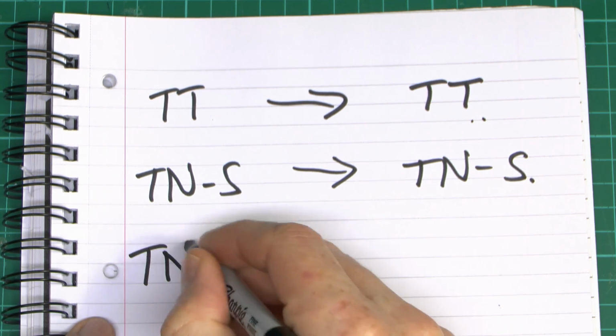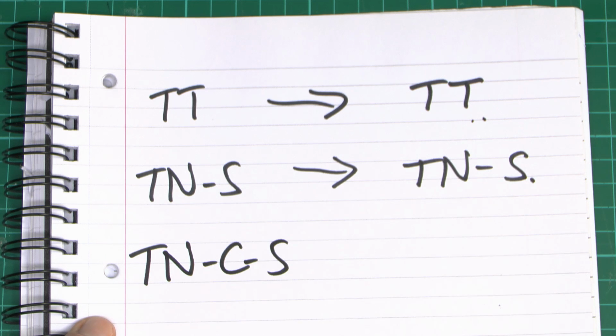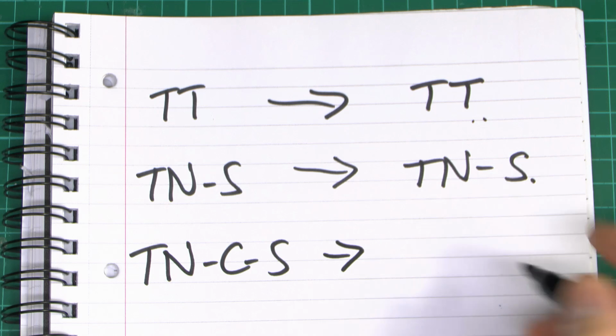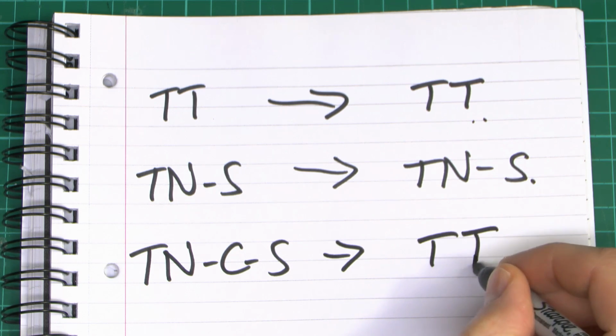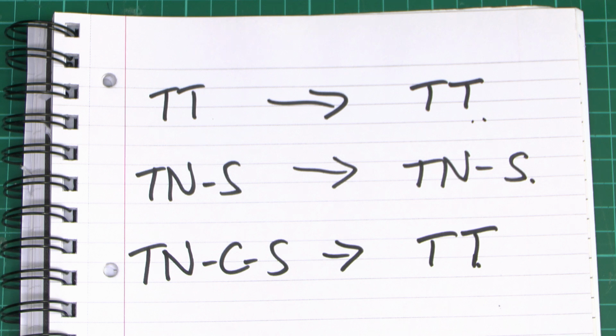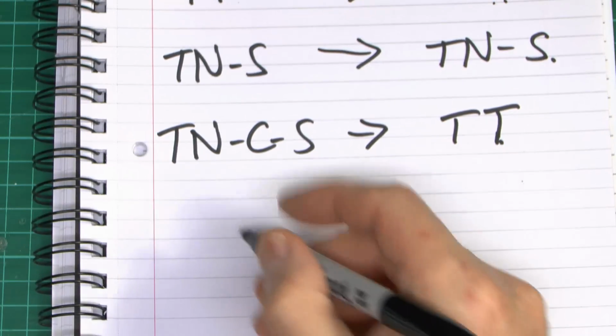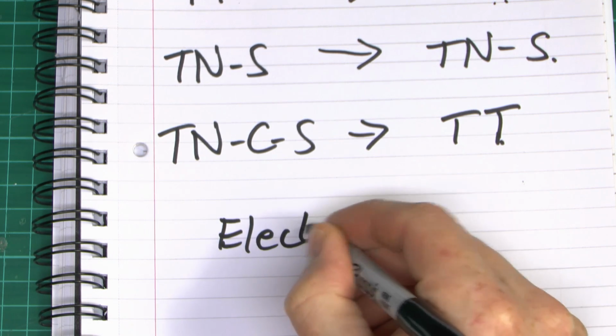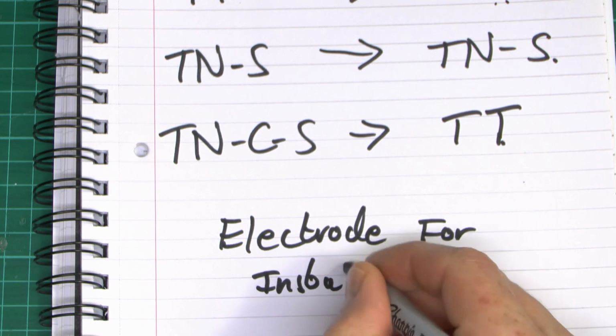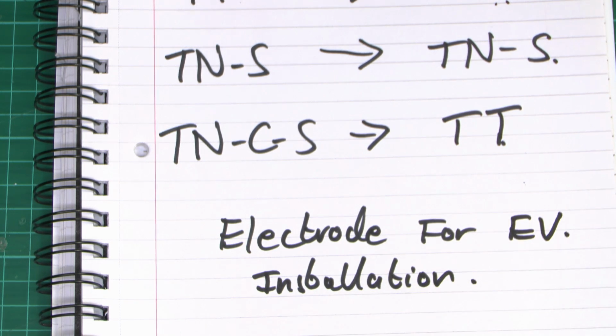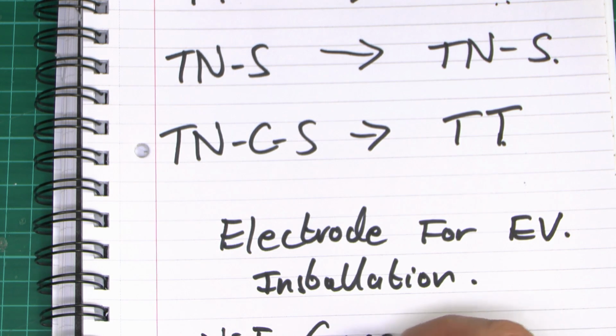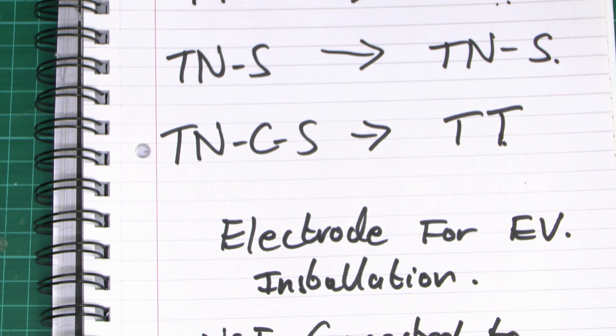And if you've got a TNCS installation, which again is pretty much the default choice for any new or newish property, your only realistic option is to use it as a TT installation, because as we saw there, those 3 things can't be used in reality. They're completely impractical, and certainly not something you're going to be using in any real situation. And by putting it to TT, what we mean is a separate electrode for the installation only. That would be the EV installation. And it is not connected to the TNCS earth.